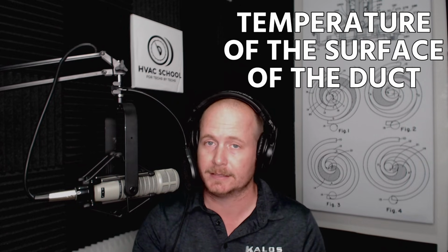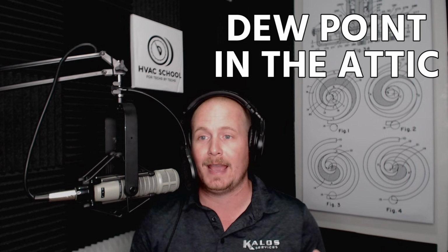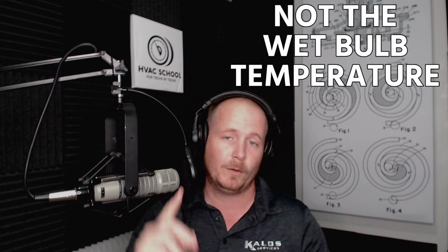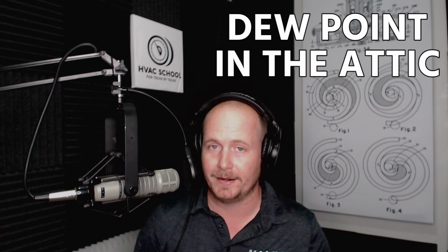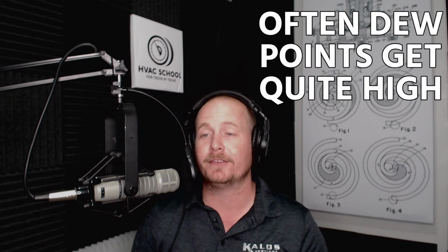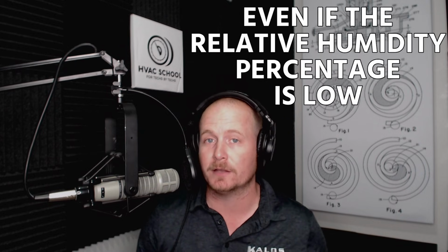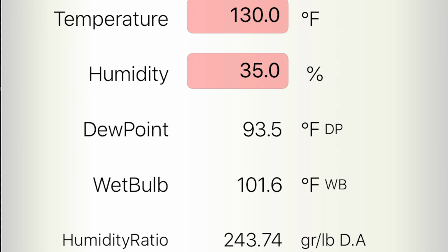So when you have situations like the video shown where you have ducts that are sweating in the attic, there's two factors. There's the temperature of the surface of the duct itself, and then there's the dew point in the attic. It's not the temperature in the attic, it's not the wet bulb temperature, it is the dew point in the attic. And one thing that you'll find often is that as an attic gets hotter, often the dew points get quite high, even if the relative humidity percentage is low. So for example, I'm using the, it's called the Psychrometer app. That's the way I know how to describe it, but I use this all the time in place of using a psychrometric chart. Just makes it nice and easy.